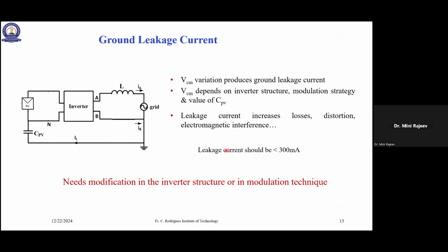So as I mentioned before, according to standards, the leakage current should be less than 300 milliampere. Whenever transformerless inverters are installed, there is a residual current monitoring system. This system will measure or sense this leakage current. And if it is more than 300 milliampere, it will disconnect the inverter system.